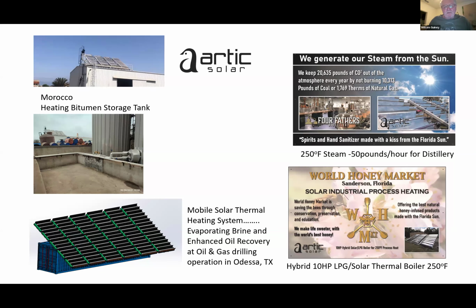So a couple of my projects: a bitumen storage tank in Morocco, where we're keeping the tar thin so you can pump it through the piping. I've done a process heating system on a honey farm, 250 degrees circulating through the facility to keep their honey hot. They have a room in the facility that has to maintain 110 degrees year round so they can pump the honey. We also provide space heating in this facility. So we installed a solar thermal system and a 10 horsepower LPG boiler to be able to provide his needs at the processing facility.